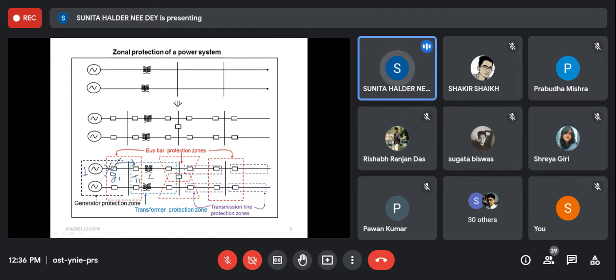But if somehow G1 fails, then T1 should wait. It should give time G1 to operate. How long? That will be set. So it is expected that G1 will operate within the 20 millisecond. So T1 will start operation after 20 millisecond.